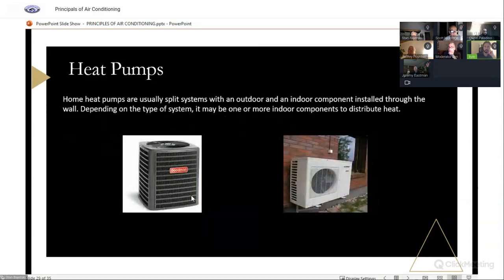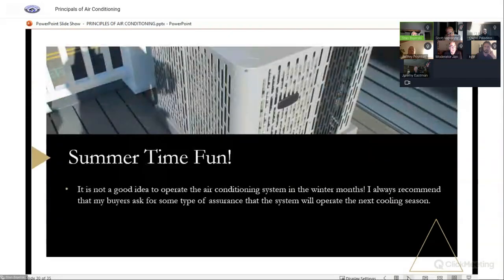This is a heat pump. You wouldn't know it. Most of the time it's written someplace on there, but this is a Goodman heat pump. This is your mini split. I don't think I've ever seen a mini split that was not a heat pump. And the rule of thumb is there's a certain temperature where you should not be operating an air conditioning system. And most of that reason is because we may be drawing liquid refrigerant back to the compressor.